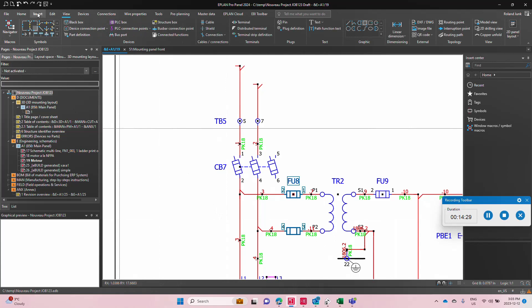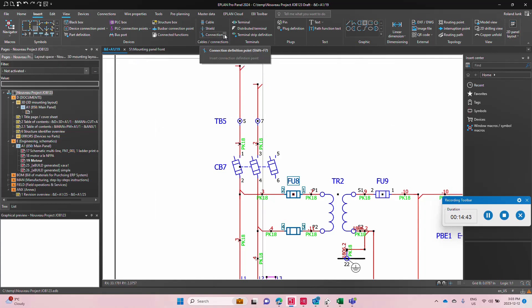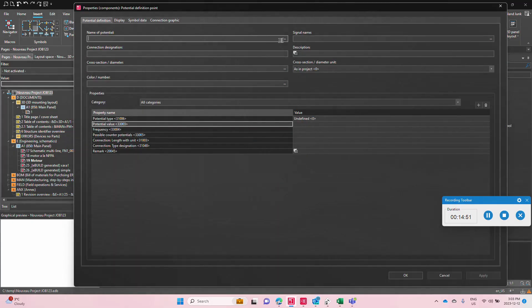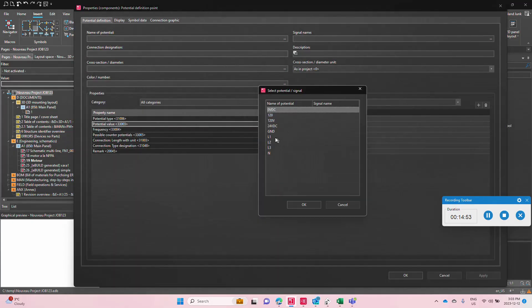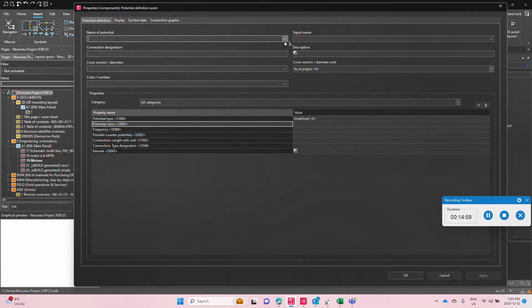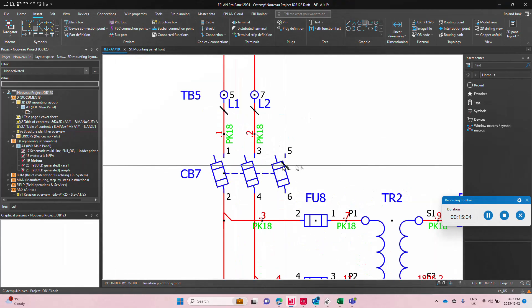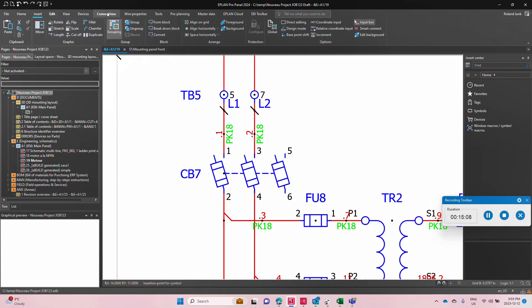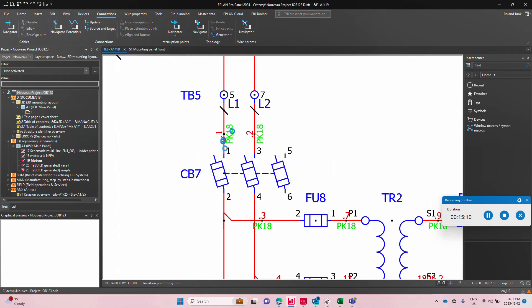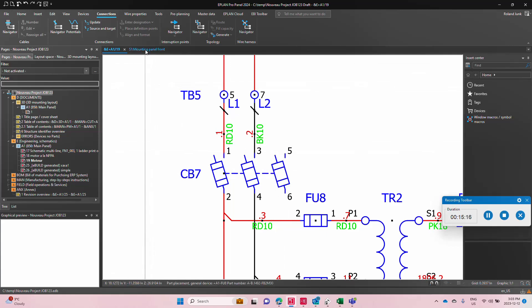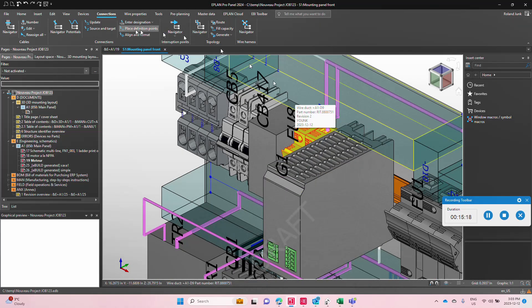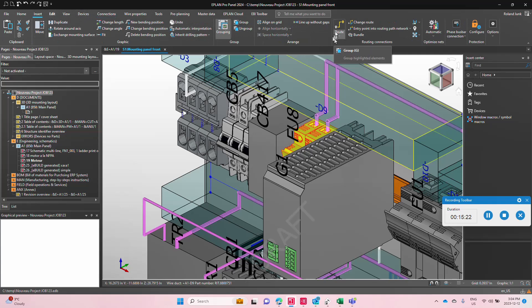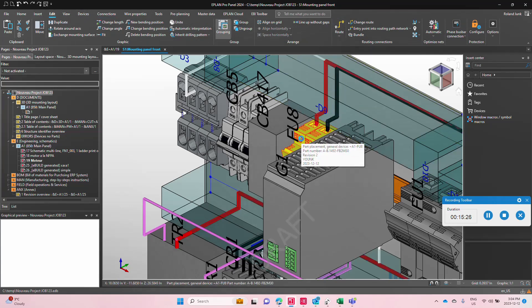Well, to get some coloring in here, I would recommend to actually assign L1 and L2. Now, these L1s and L2s are actually defined through some specific connection information, and we call them here potential definition points. So you could actually go up here and say this is part of L1. L1 has a specific coloring gauge already assigned in previous pages. And this here is actually L2. And it is also colored and assigned with some colors. You will see this right away. If you run here connections update, you will see how the colors actually change and even the gauges change. And that immediately, if you go back here to the routing and you try it out again, will immediately regenerate those as the new wire colors and gauges, in this case, black and red.